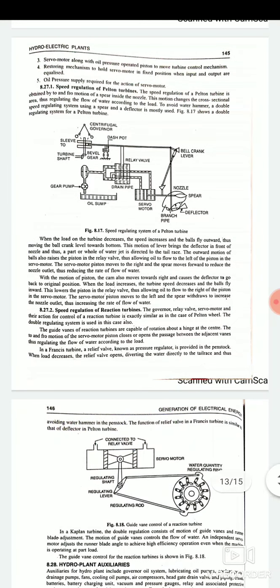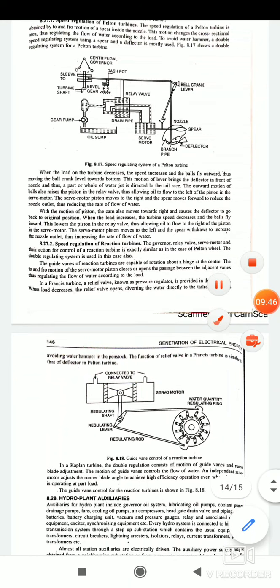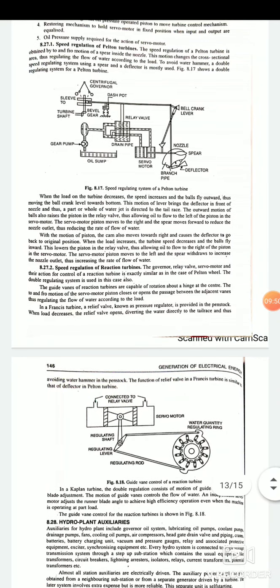Next is your speed regulation of a Pelton turbine. This is the systematic diagram of a speed regulating system of a Pelton turbine. When the load on the turbine decreases, the speed increases and the balls fly outward, thus moving the bell crank lever towards bottom. This motion of the lever brings the deflector in front of the nozzle, so a part of the water jet is directed to the tail race. Outward motion of the balls also raises the piston in the relay valve and allowing oil to flow to the left of the piston in the servo motor. The servo motor piston moves to the right and spear moves forward to reduce the nozzle outlet, thus reducing the rate of the flow of water. So in this way we can control the flow of water with the help of speed regulation mechanism.